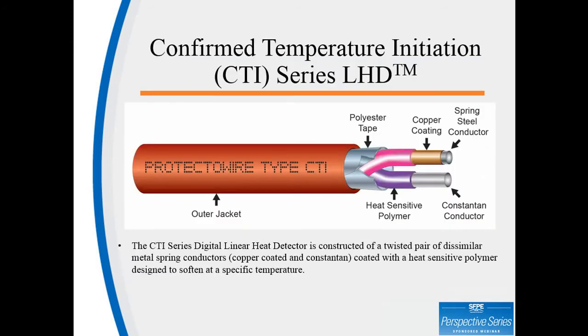Confirmed temperature initiation, or CTI Series LHD, is a new technology in the LHD market. Although it appears to be the same construction as regular digital LHD, it is made from different materials. The CTI Series digital linear heat detector is constructed of a twisted pair of dissimilar metal spring conductors, copper-coated and Constantan, coated with a heat-sensitive polymer designed to soften at a specific temperature.